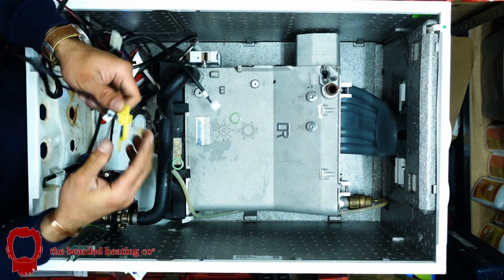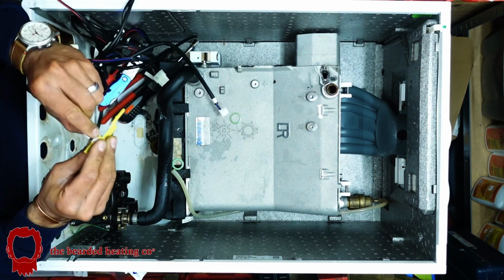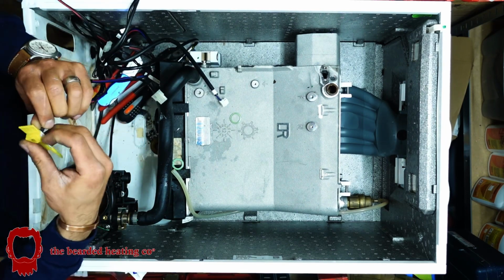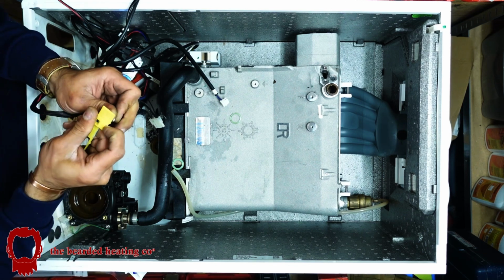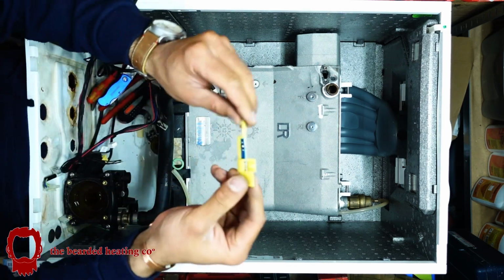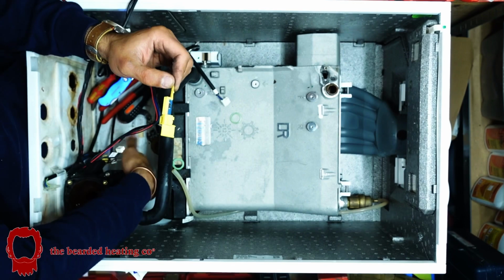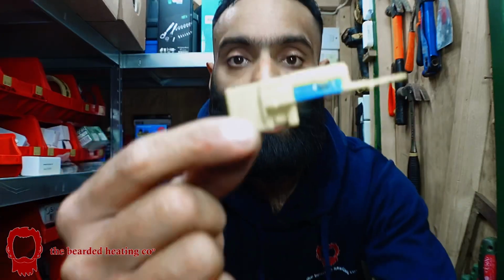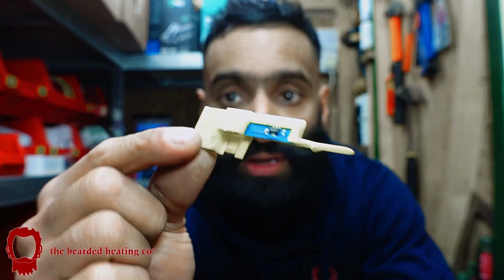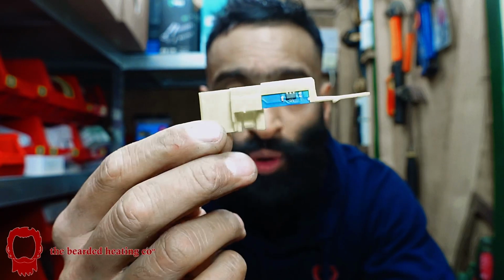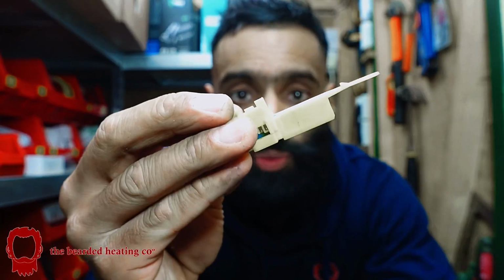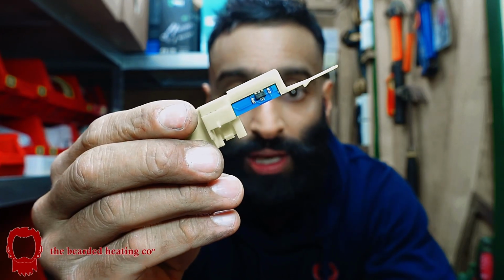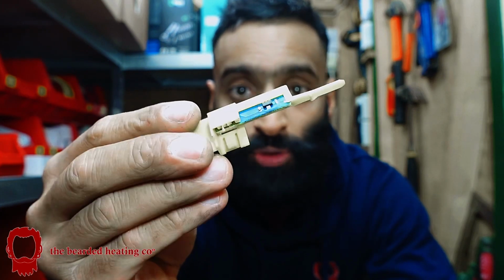I was wondering where this was and what kind it would be. I've never replaced one myself, but let me get it off. So you've just seen me pull it off the back of the pump housing. This is a Hall sensor - this is what detects the cold water coming into the boiler and triggers the boiler to fire up on hot water demand.